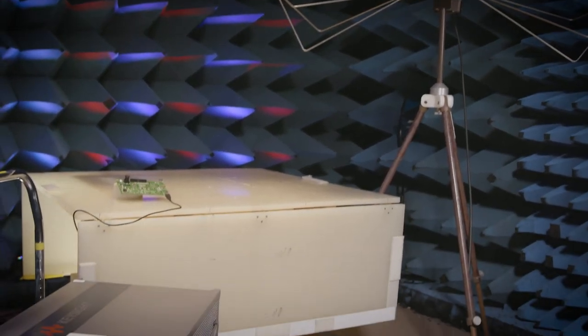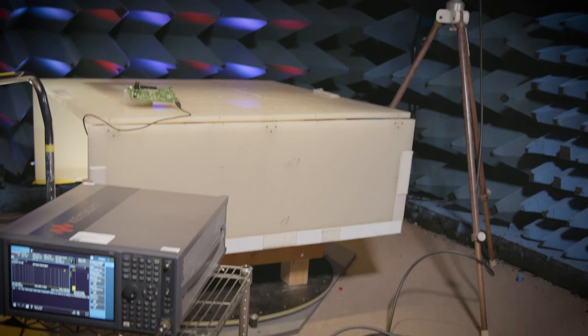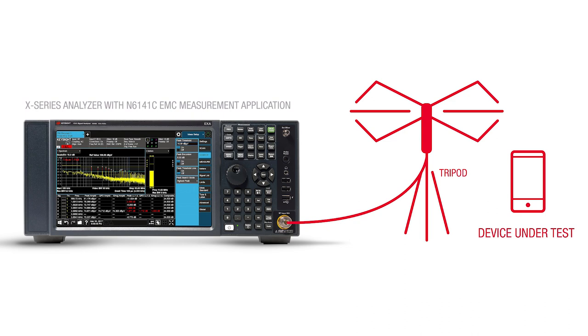Here's what our radiated emissions test setup looks like. You'll need a large area away from other electronic equipment to avoid electromagnetic interference that can disrupt your testing and lead to inaccurate results. Most commonly, your device will be placed at a distance of three meters away from the antenna, which is connected to the EMI receiver or spectrum analyzer outside the chamber. Stay tuned for the next episode of the ABCs of EMC series where we'll perform an EMC pre-compliance test on our device.